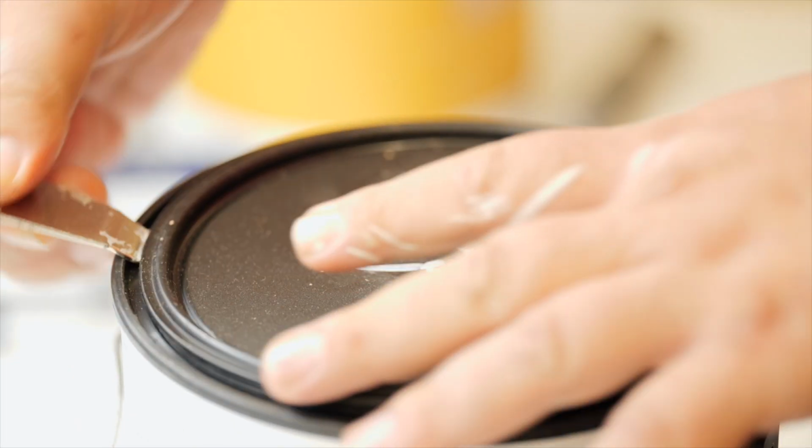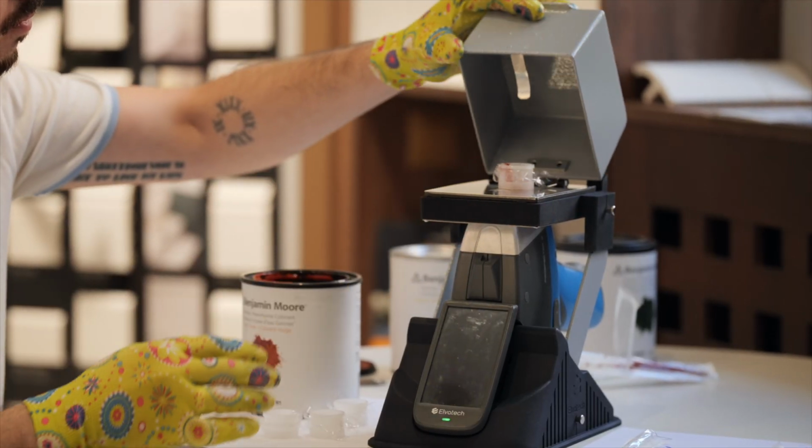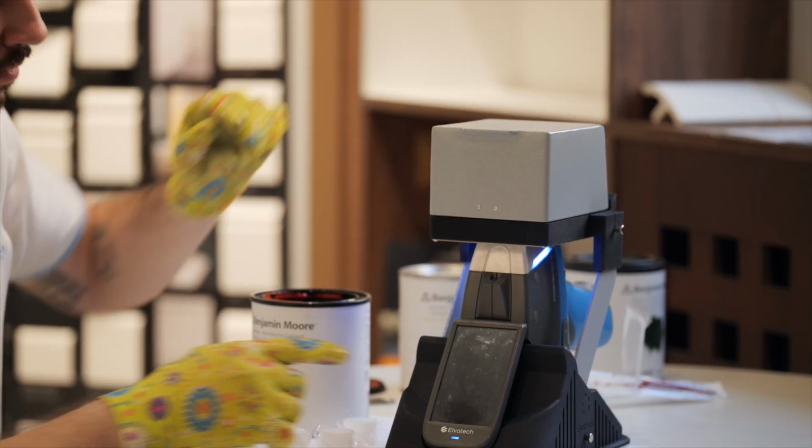You cannot determine the lead content in any material without specialized equipment, and X-ray fluorescence analysis is one of the key and most reliable methods to control substances in any kind of material. This method is very simple for lead analysis because it doesn't require any sample collection or sample preparation. All you have to do is direct your sample to the measuring window of the device and start measuring. Everything else will be done by the analyzer. And now we are going to the place where all the magic happens. So follow me.